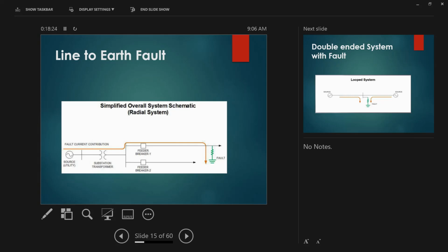That's why when we do maintenance, sometimes the scope of work says earth continuity, loop impedance, fault potential, because if you have a fault in the field, the only way it can be received by the relay is with a better, lower resistance, like below 0.5, and the impedance should be very low as well for you to reach the specific fault. That's why we check that. It doesn't mean that because I'm doing only earth testing, I don't care about the rest; all the services that we do are consolidated with each other. That's why we fail the installation if it doesn't meet the requirements, and we pass it if it passes the requirements of the standard.